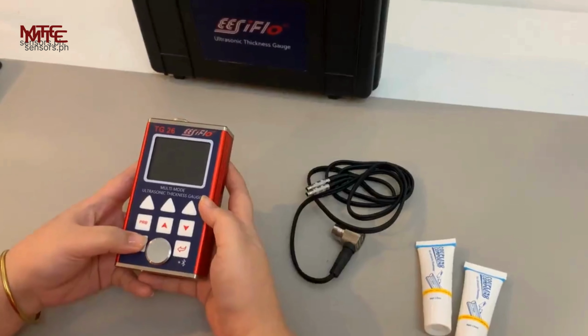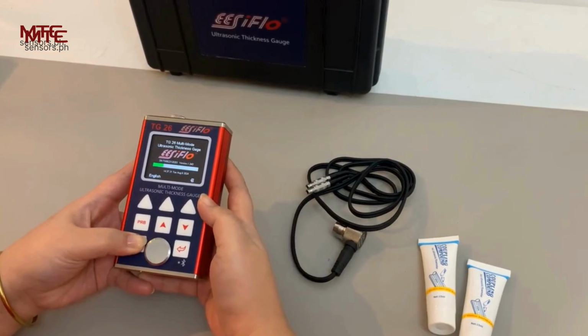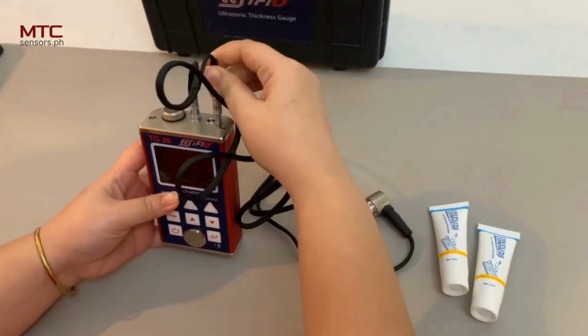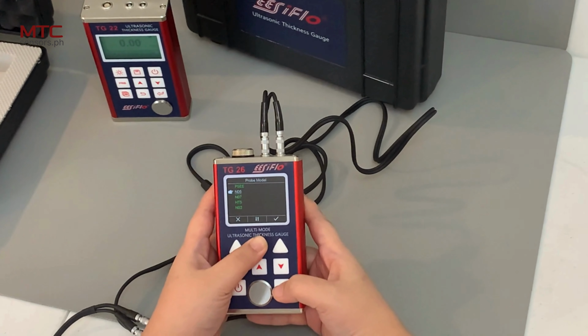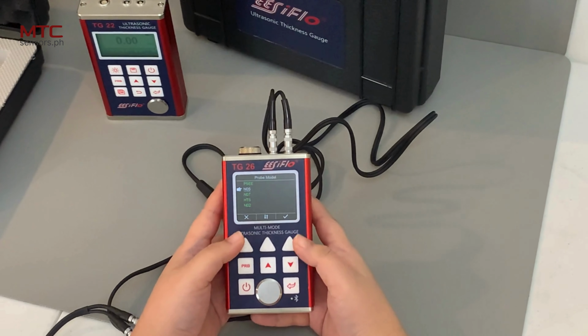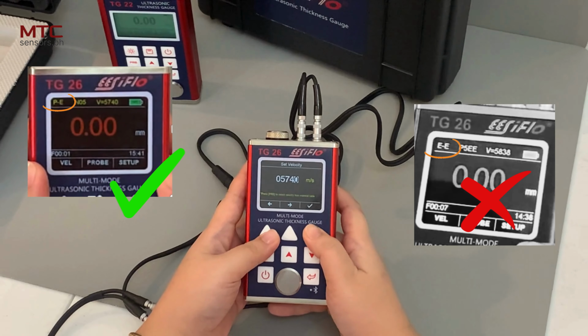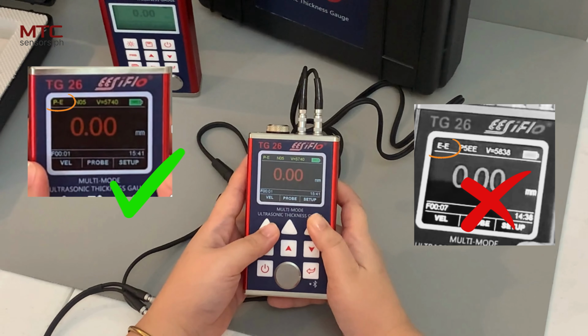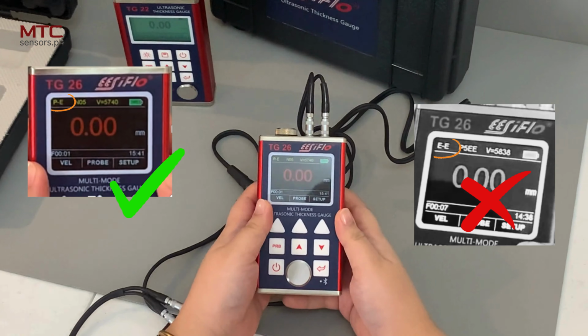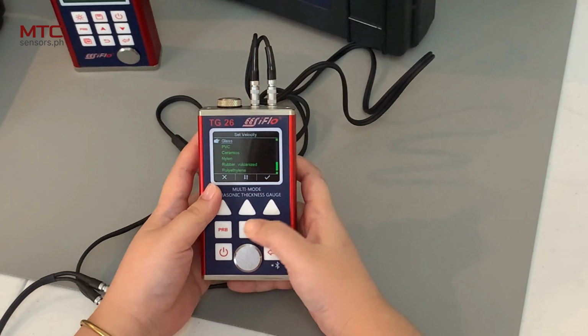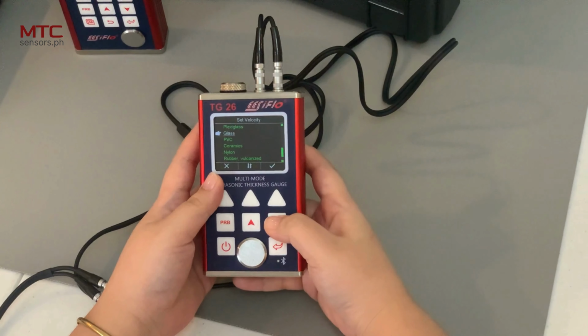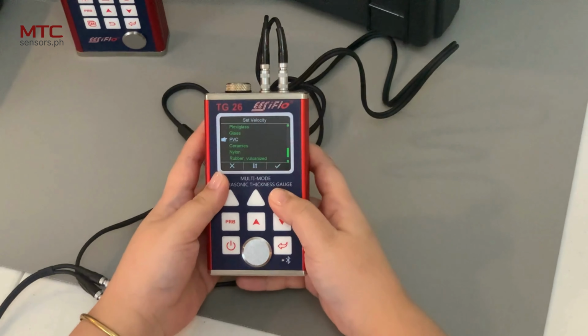To start the instrument, press the button until the display activates, then connect the probe to the device. Next, set the work mode and ensure the correct probe model is selected. Perform the probe zero operation only in pulse-echo mode. Do not do this in echo-echo mode. For accurate measurements, set the correct sound velocity and enter the nominal thickness.